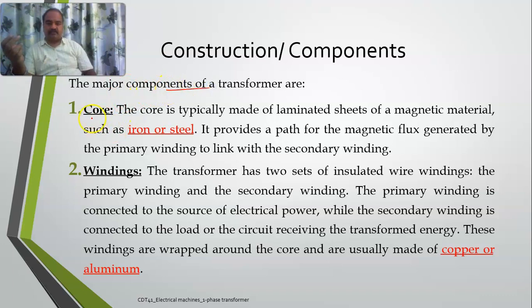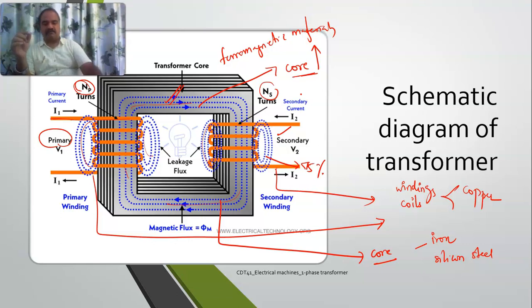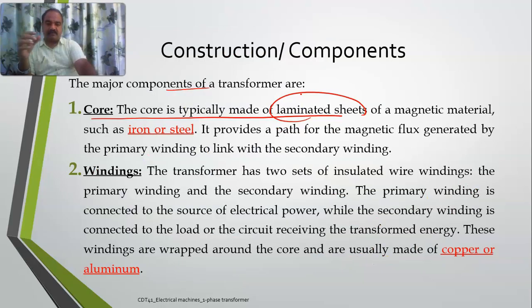The core is a strong ferromagnetic material — you can use iron or advanced steel materials like silicon steel. The important components are: one, the windings or coils which are made up of copper; and the other is the core which is made up of iron or silicon steel. Laminated sheets are used for the core because if you use a single block of material it may get heated. To avoid that, you take parts of steel with an insulating or plastic material between the laminations.